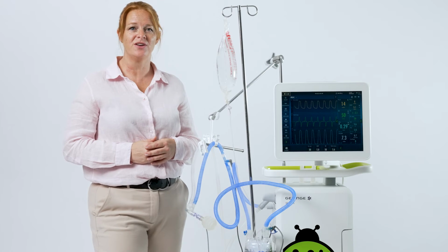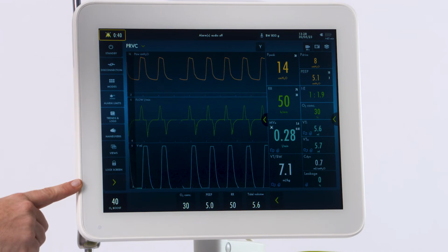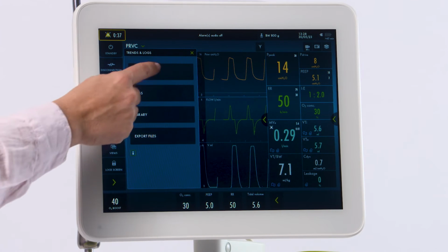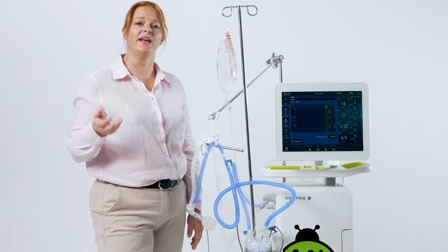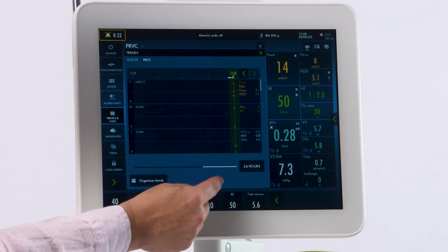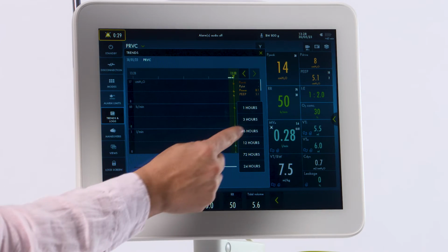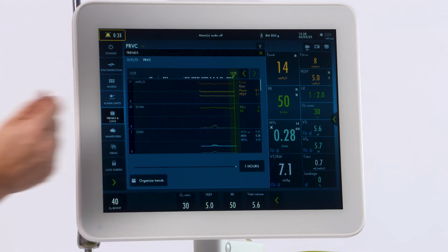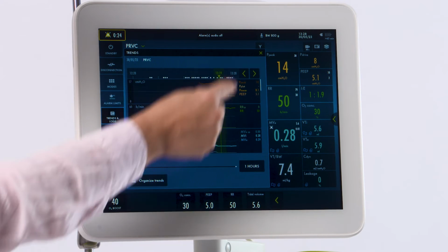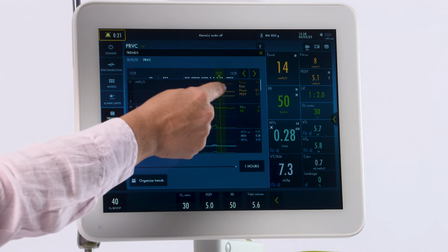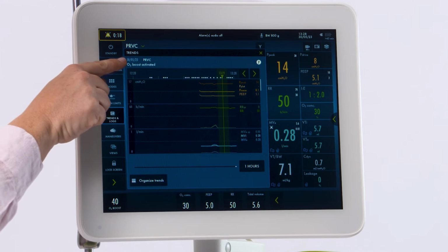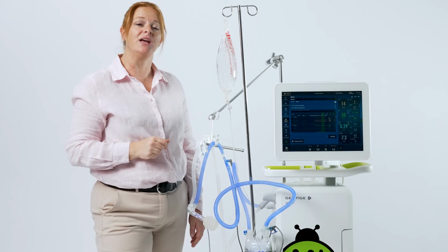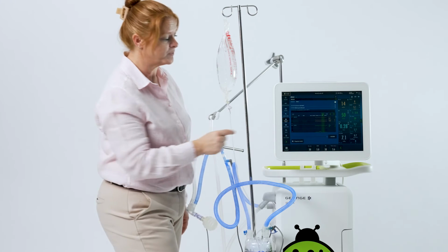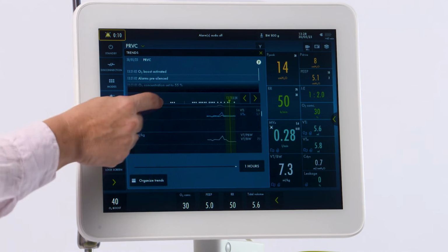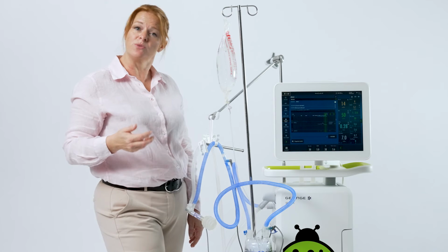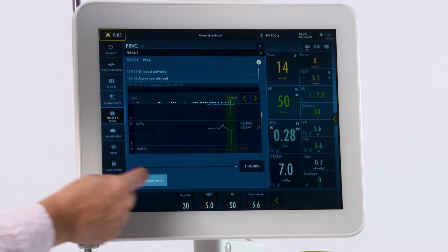The trends and logs are located in the menu screen. Select Trends and Logs. At the top will be your trends. You can look anywhere from an hour up to 72 hours of time by selecting on the side. You'll notice your trended values. Wherever your cursor is, those are your numbers. Gray hash marks at the top mean an event occurred. You can touch them and it will list all events in that minute. Simply scroll through to see different things that are trended. If you'd like to reorganize those, select Organize Trends.